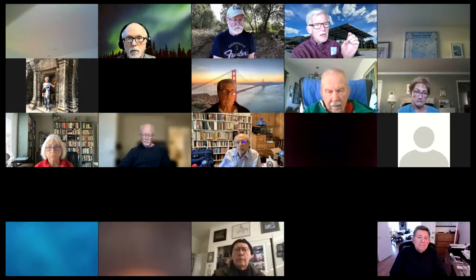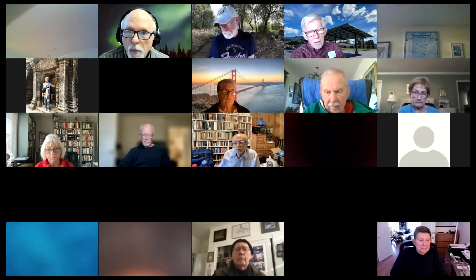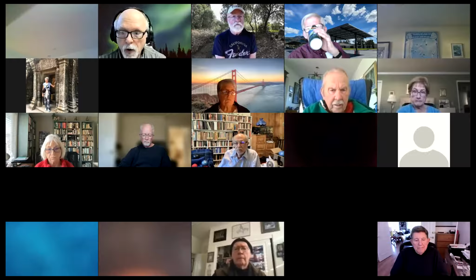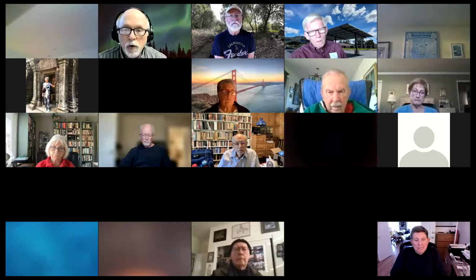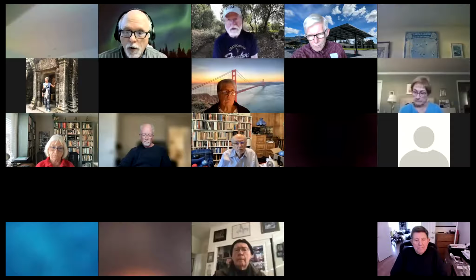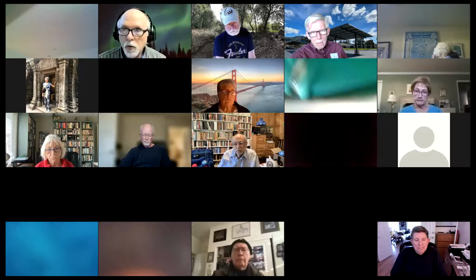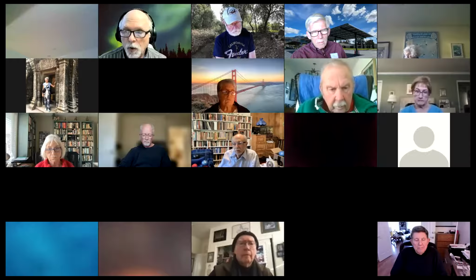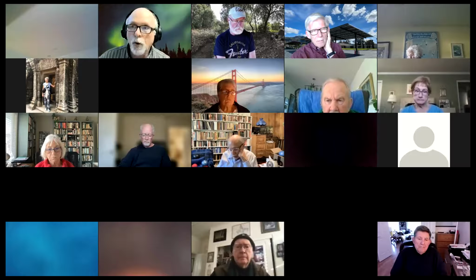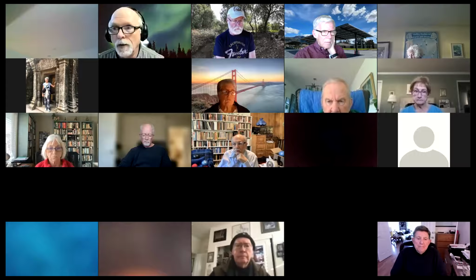Okay, Bruce, you're next and then Phil. Okay, can you hear me okay? Yes, I can. First of all, just sort of confirming what we have now. We have the solar panels, we have the switching, and we have a large generator. It looks to me that the generator is only going to be used in the eventuality that PG&E cuts us off. Yep. And so under normal circumstances, what we have now is the larger equivalent of a residential grid-tied system, where basically you generate all the power you can, but you're using the PG&E grid as a super battery or energy storage to supply you anything extra and to take up anything extra that you generate. Is that fair to say?